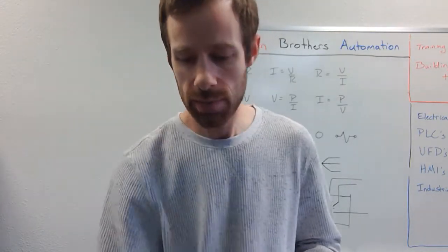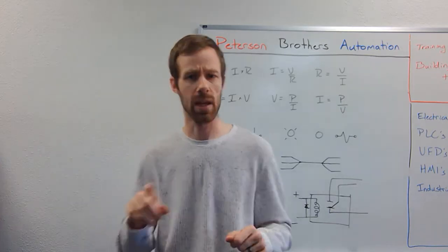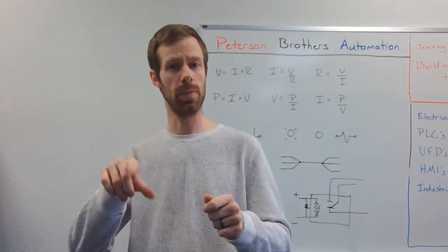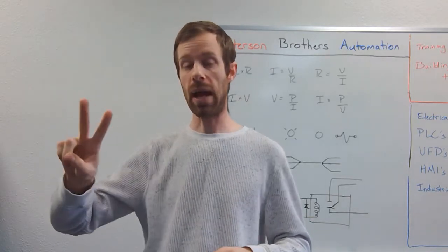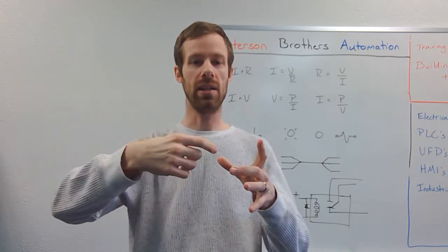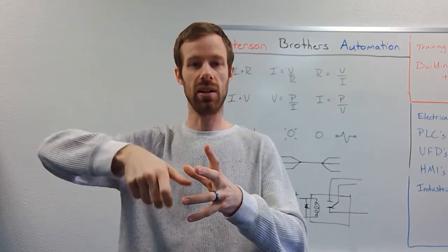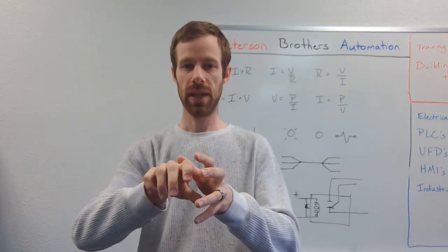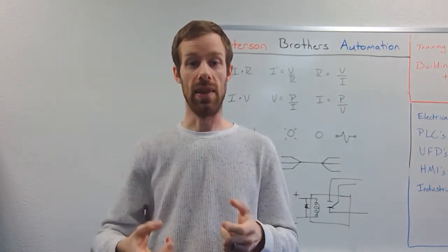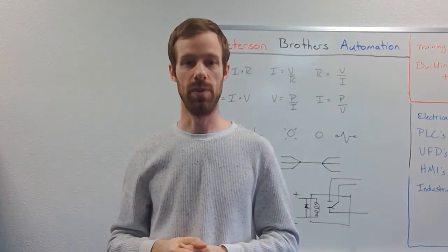Power distribution. Sometimes on schematics, you'll see it abbreviated PDB, which stands for power distribution block. And those can be two different types. A power distribution block can be one giant hex-keyed lug that tightens down on a huge wire, and then on the other side of it is a whole bunch of other holes with hex-keyed, tightened down set screw lugs, and that's made for massive power distribution.